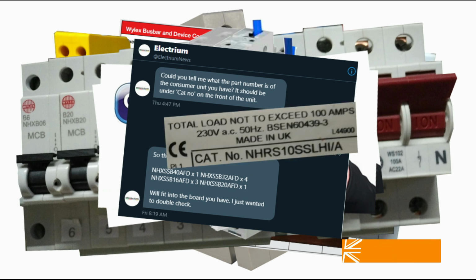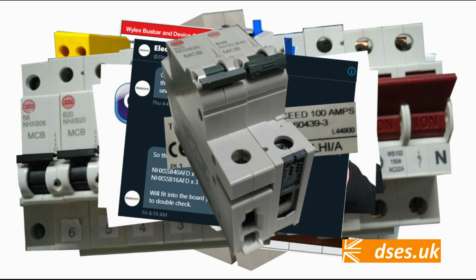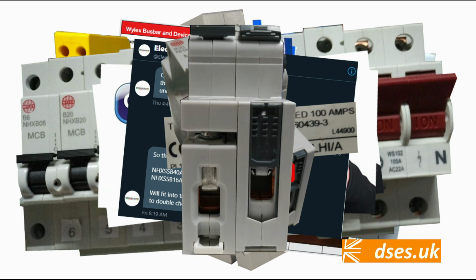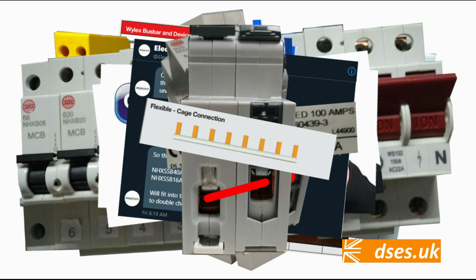However, I remained concerned because if you compare the NHX devices I currently have in my consumer unit with the NHXL range of devices, you'll see that not only do NHXL lack compatibility with the balcony busbar, precluding their installation in DB2, but when placed side by side, their connection holes don't line up, meaning they couldn't mix and match on the same flexible busbar in DB1. What's NHXL got to do with the price of fish, and how's it a problem if I'll be changing all my devices in DB1 and putting in a new flexible busbar, I hear you cry?